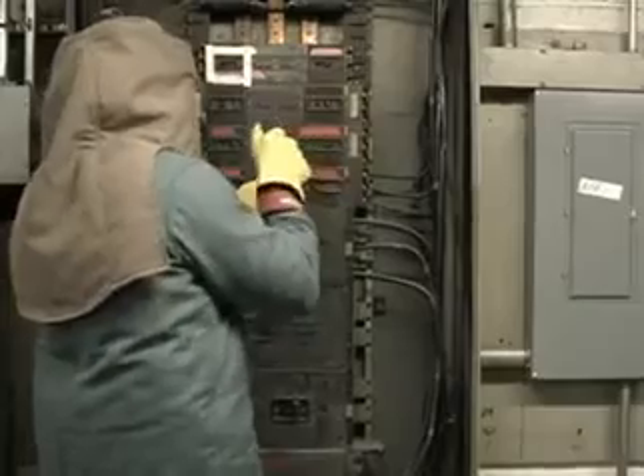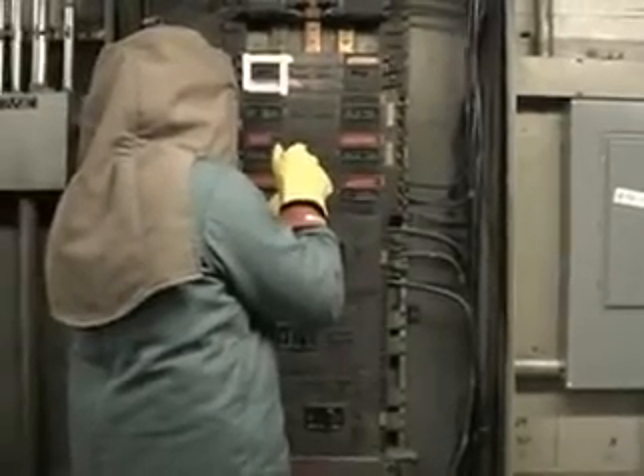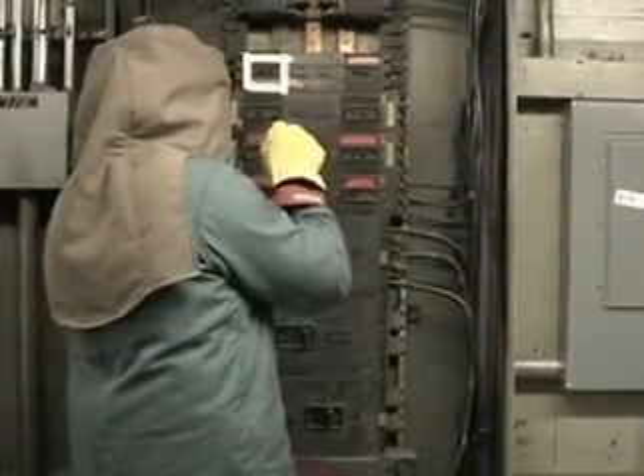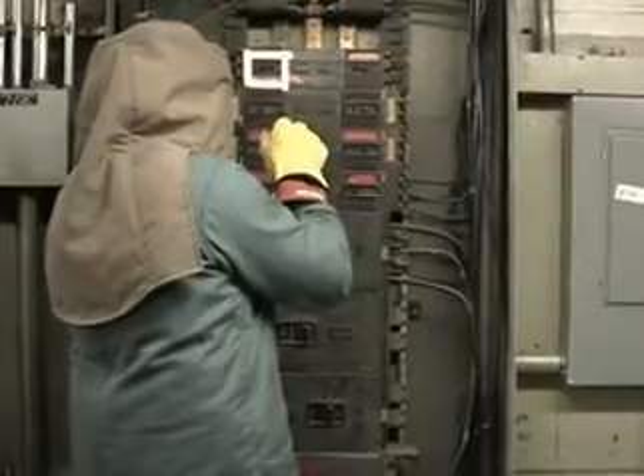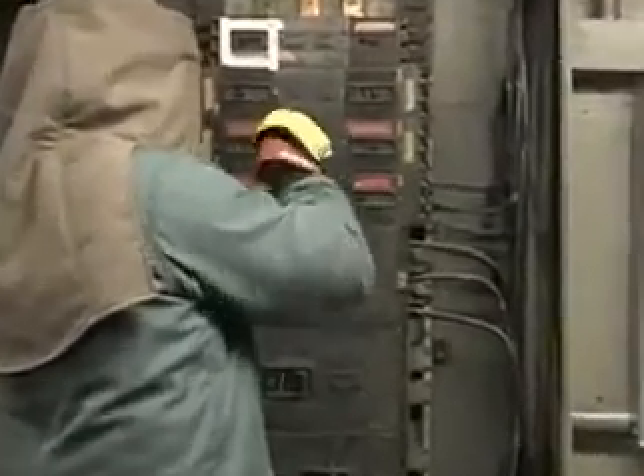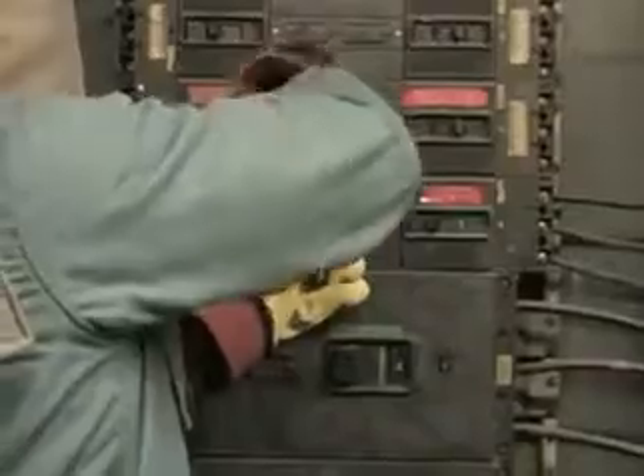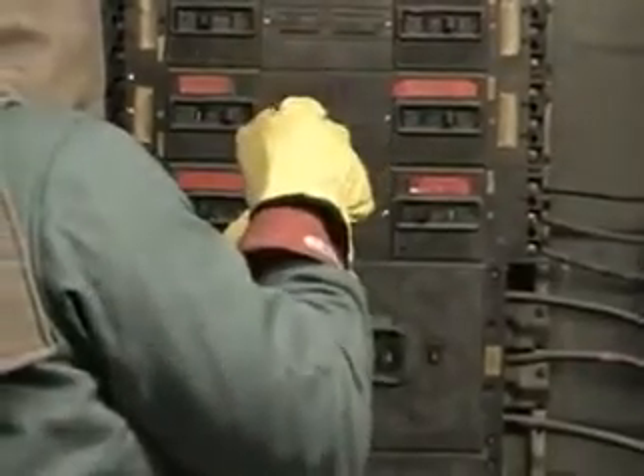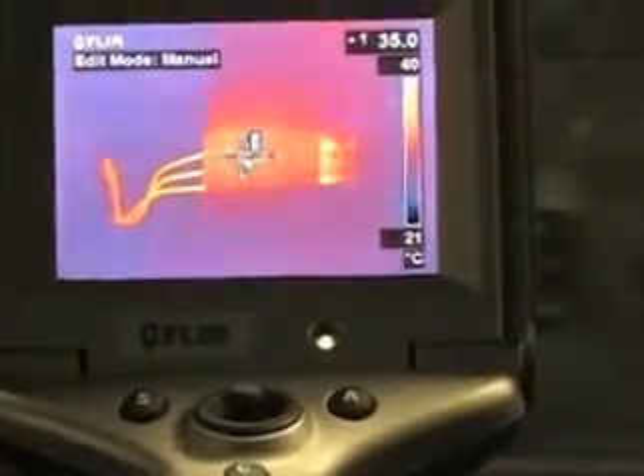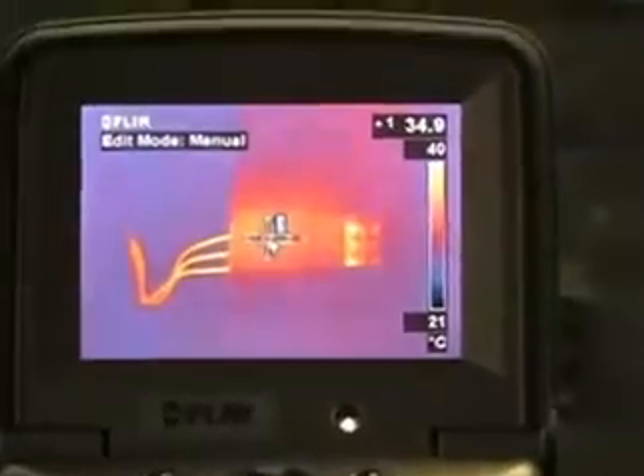To ensure accurate temperature readings, a cover is removed to view the bus. Infrared thermographic imaging requires a line of sight to obtain any heat information. To take this one step further, the NFPA 70B strongly recommends all cover removal to obtain accurate temperature measurements when utilizing infrared thermography.